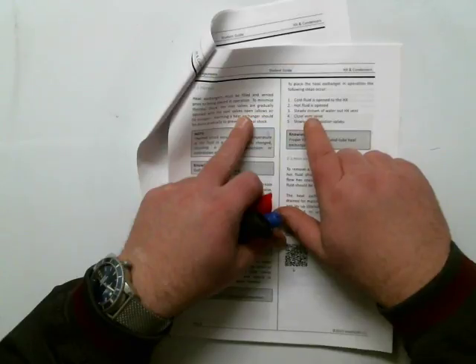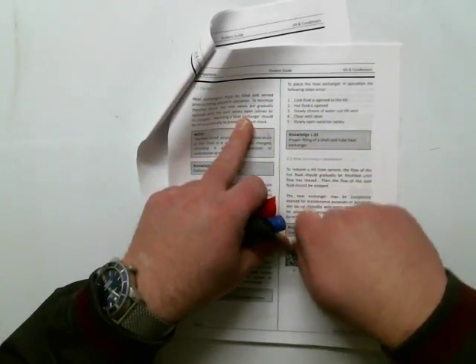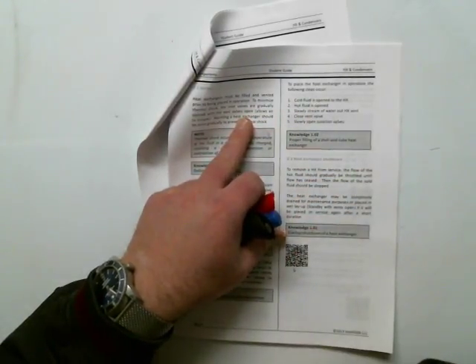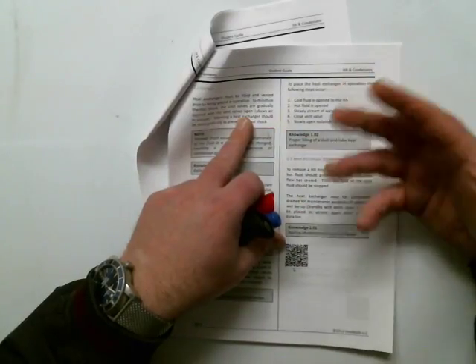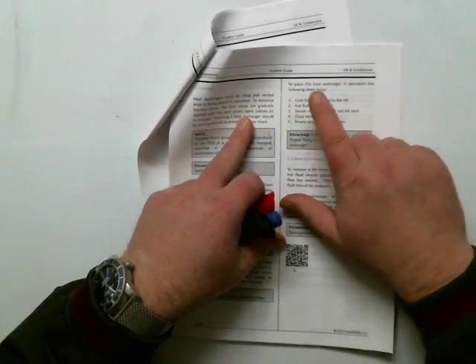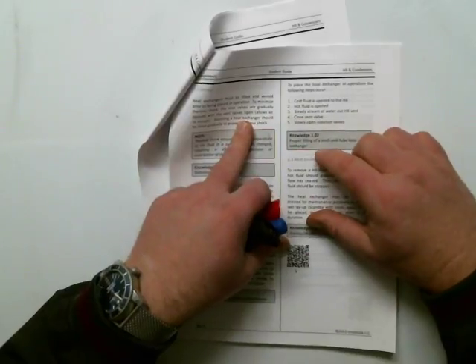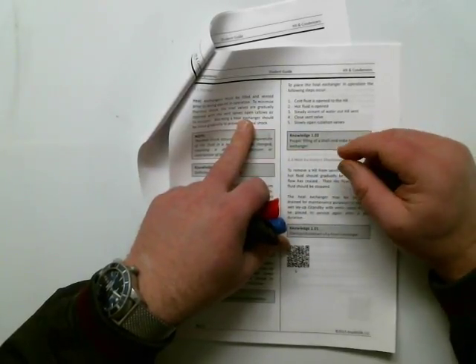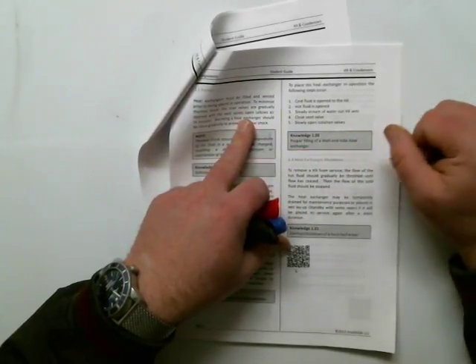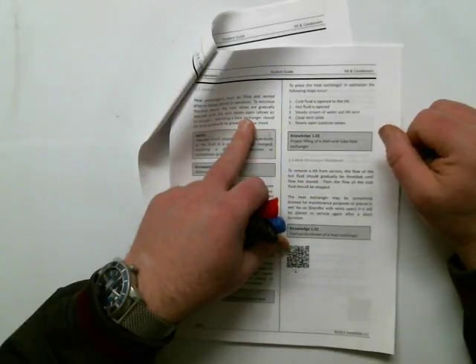And many heat exchangers will have operational vents, but these would just be fill and vents for placing it in service prior to operation. And then shutting down is essentially the reverse order. What's key to note is the colder fluid is always the first introduced to the heat exchanger and the last one removed from service. All right?